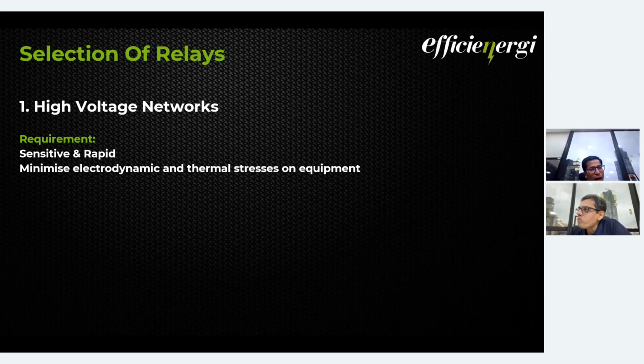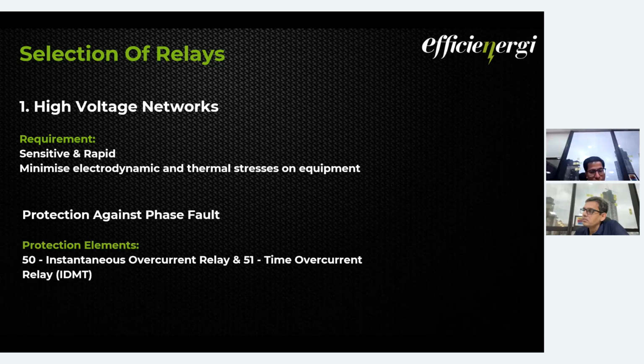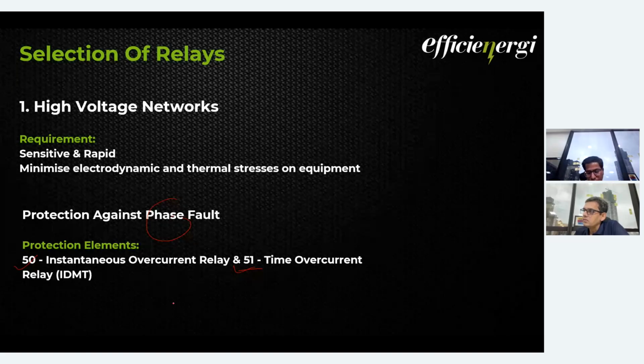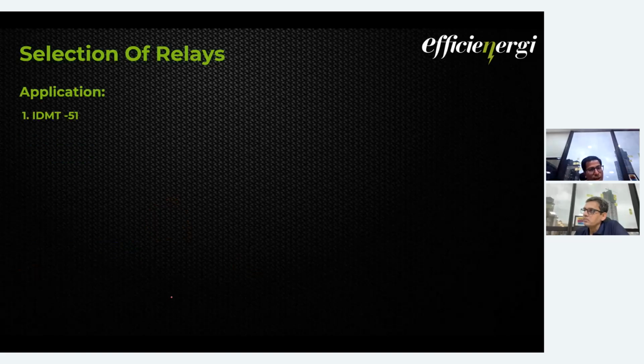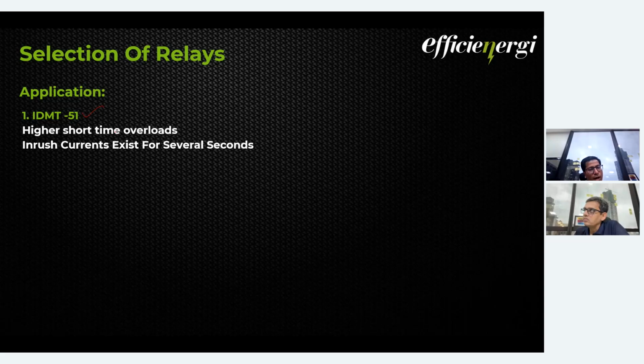We all know that in high voltage networks, the main requirement is that the relay has to be sensitive, rapid, and minimize the electrodynamic and thermal stresses on the equipment. For protection against phase fault, we are using 50, that is instantaneous overcurrent, and 51, that is time overcurrent, IDMT. I have already explained the characteristics of these relays in the previous webinars. For application of 51, we have to go for 51 where we are expecting short time overloads, overloads more than a pickup value but for a very short duration.